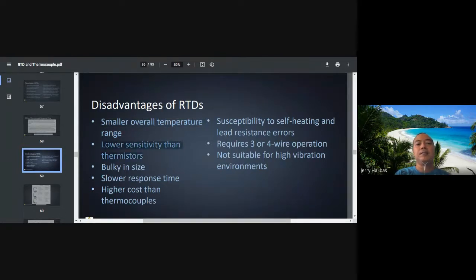Okay, it's not that sensitive. An RTD is not sensitive; the thermistor or thermocouple is more sensitive. Because it is not sensitive, that is the usual issue. Its response time is slower. Then it is more expensive than the thermocouple and the thermistor. What else? It requires 3 to 4 wires, a disadvantage. Because of that, it is not suitable for high vibrating environments, since with four wires, the wires can move.